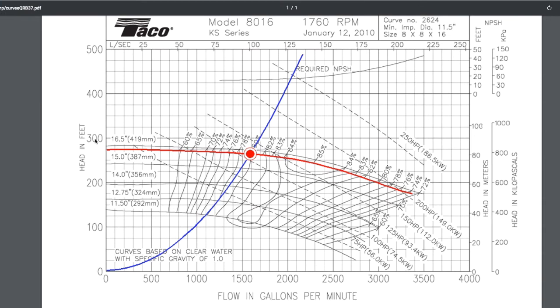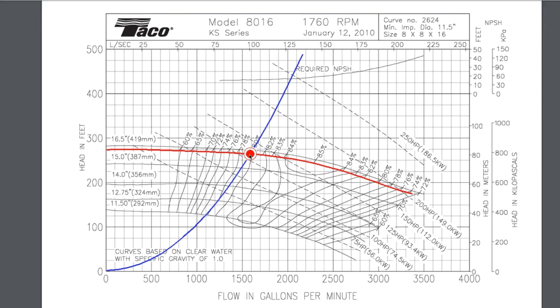The first thing we look at is the head-flow curve, which tells us what head rise across the pump we'll get at different flows in gallons per minute. The red curve shows that head falls off a little with increasing flow. Starting at 1,585 US gallons per minute — or 100 liters per second, the same flow rate — we get a head of around 260-some feet, or about 80 meters. That's a check that our calculations were correct.